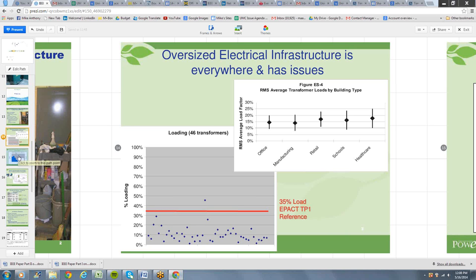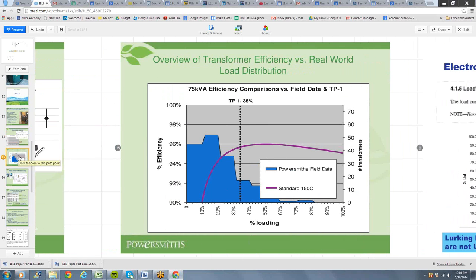And as you can see on the next slide, that has a significant impact in terms of operating efficiency in real life compared to what you would think of at a 35% load point. So here in blue, you have the loading profile of transformers, stacked to the left, light load, that 35% reference point of the legal requirement, and then overlaid on top of that is a typical transformer efficiency curve, which you can see peaks in the 30, 40, 50% range, but drops off very sharply at lower loading, and that's a problem because realistically, that's where transformers are running. So if you're looking at the technical data sheet of a transformer and you go, oh, it should be this efficient, in fact, once you run it, it's substantially lower than that.